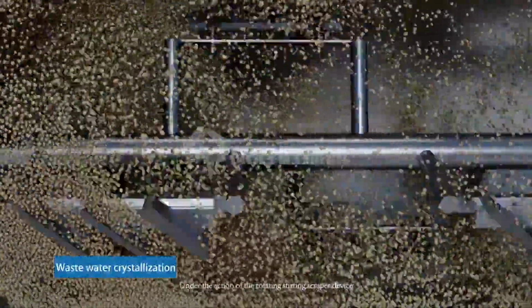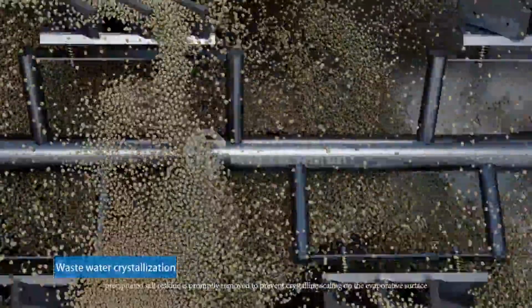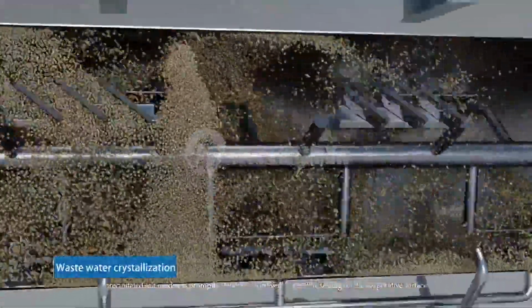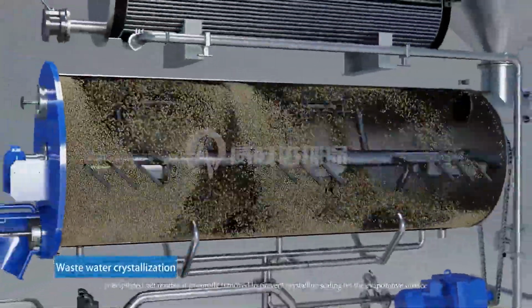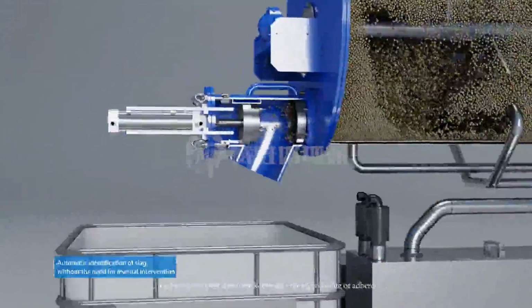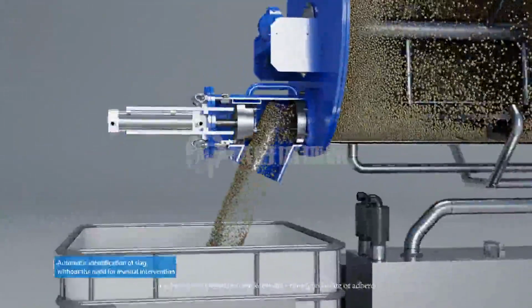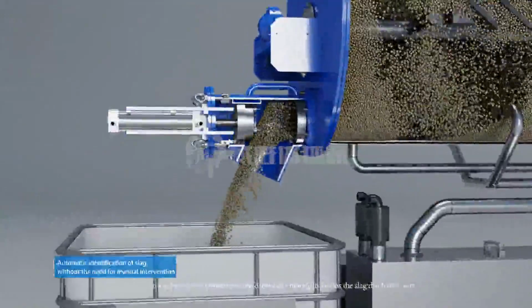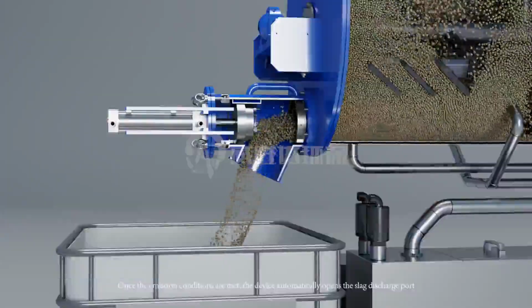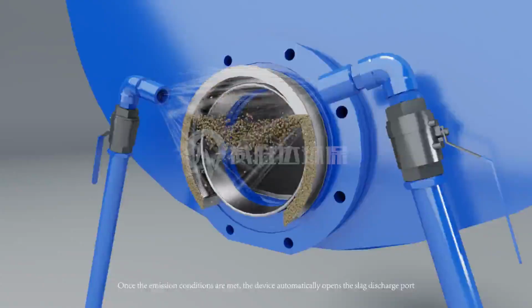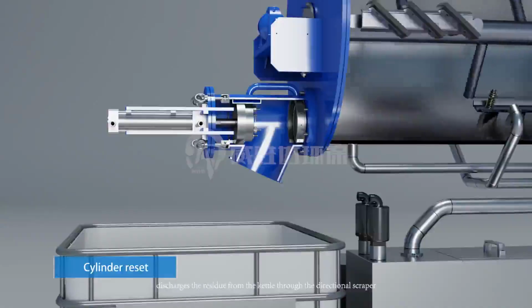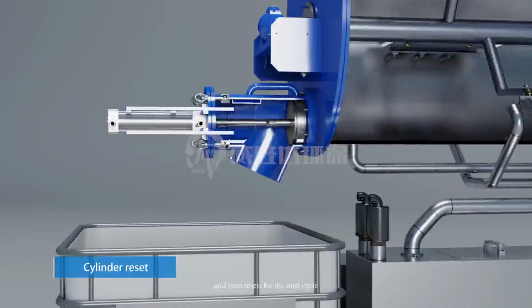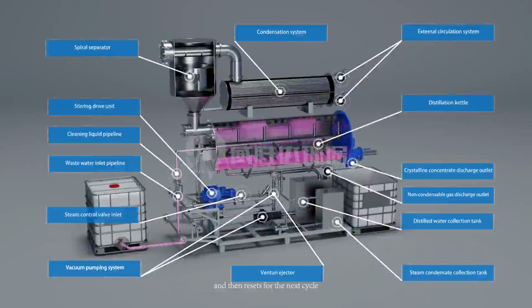Under the action of the rotating stirring scraper device, precipitated salt residue is promptly removed to prevent crystalline scaling on the evaporative surface and ensure that residue in the kettle does not agglomerate or adhere. Once the emission conditions are met, the device automatically opens the slag discharge port, discharges the residue from the kettle through the directional scraper, and then resets for the next cycle.